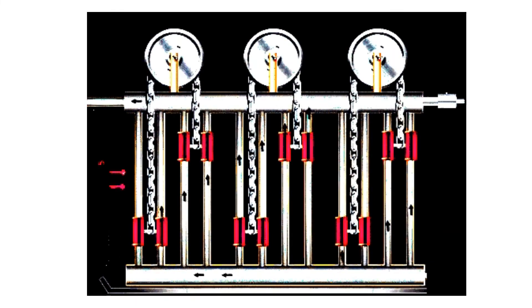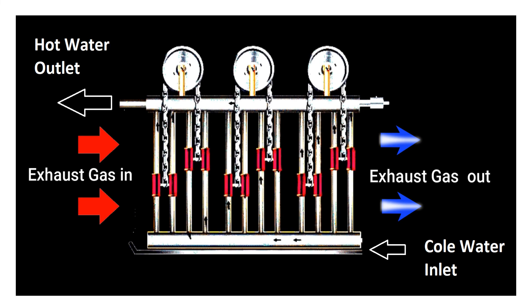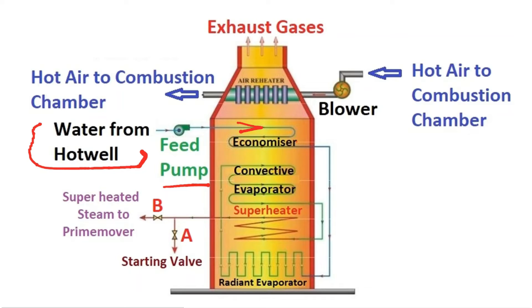The heat exchange between the water and flue gases through the economizer coil increases the temperature of the water. This hot water is then supplied to the evaporator, so less heat energy is required. The economizer improves the overall performance of the boiler.